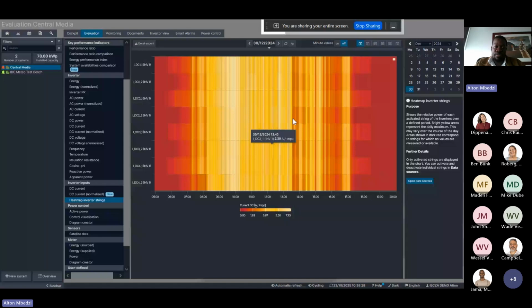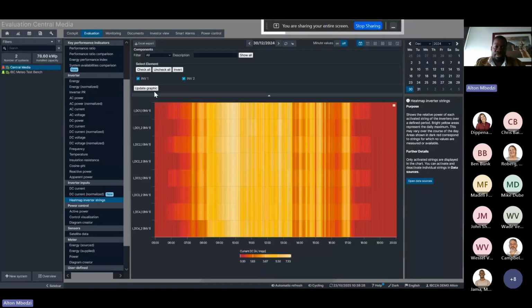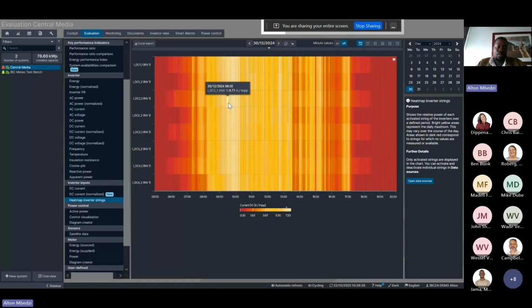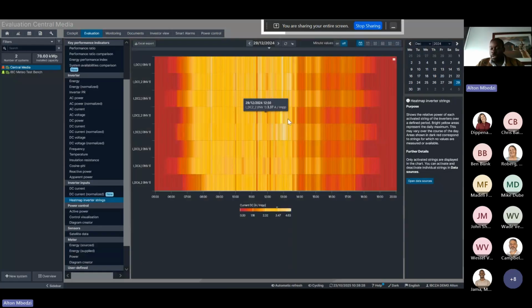Let me just see if I can pull from inverter number 2. Check all, update graphics. Okay, perhaps inverter number 2 doesn't have this capability. I'm just not going to mention the inverters by name - we're not here to talk about the inverters, but I do know the inverter that was inputted here. So inverter number 1, there we go - we can see the inverter strings. Have a look, everything looks perfect. If one was down, you probably have a guy go there already with fuses to say, just take a 20 amp fuse and look at inverter number 1, DC string number 1. So this is very helpful for fault finding - very good, useful tool, easy quick visualization. Instead of having to look at the values, you just go and look at the heat map, everything's already there.